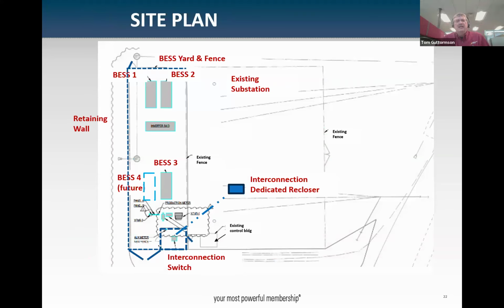This is a plot plan of the site. Connexus Energy owns all the existing land where the substation is, and our substation is bordered by this fence line. There's enough space at the back of the property to carve out some land — we cut dirt out and put in a retaining wall sufficient to fit the 3 battery units, the transformer and inverter, ancillary equipment, the disconnect switch, and room for a 4th battery, all in that area in the back. You can't see it from the road very well.